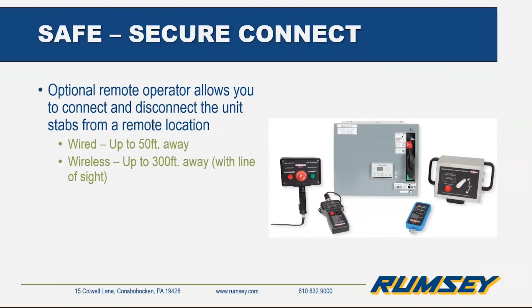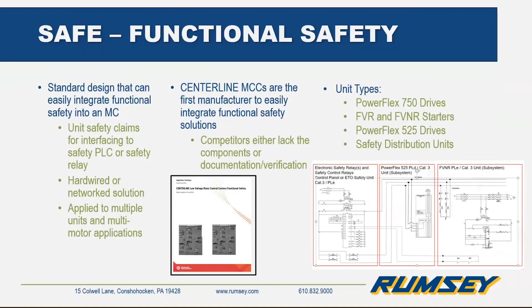So here, this is the newest safety feature in Allen Bradley MCCs, and that is the incorporation of functional safety in certain unit types. Rockwell is actually the first manufacturer to accomplish this because they have both the components and the documentation for it to be completely validated. And as of right now, functional safety can be provided in certain VFD and starter units, and we'll go through each of these in the next few slides.